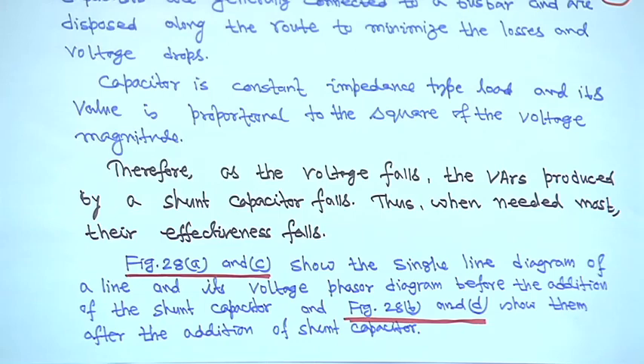When a capacitor is connected at a 33 kV bus bar, and you buy a capacitor from the manufacturer rated at say 5 MVAR, that rating is specified at 33 kV. So when voltage is 33 kV it will inject 5 MVAR. Generally, the voltage at a 33 kV bus bar may not be exactly 33 kV — it may be 32, 31, or 30 kV. Since reactive power injection is proportional to the square of the voltage magnitude, if instead of 33 kV the voltage is 30 kV, the reactive power injection will be (30/33)² × 5 MVAR — less than 5 MVAR.